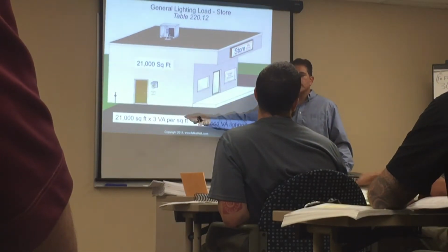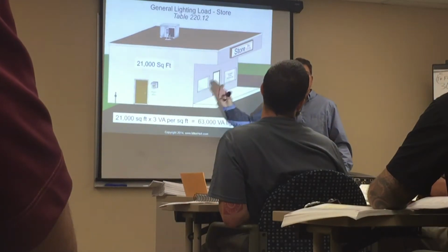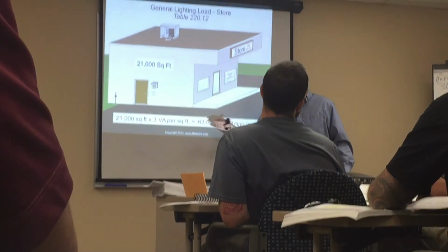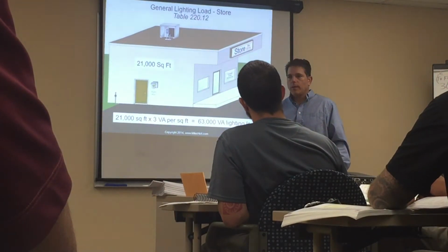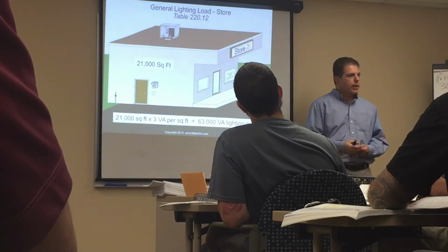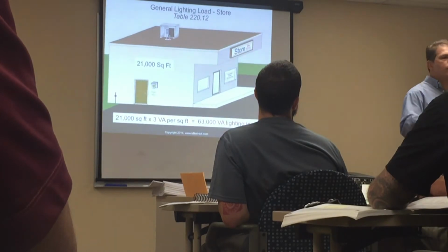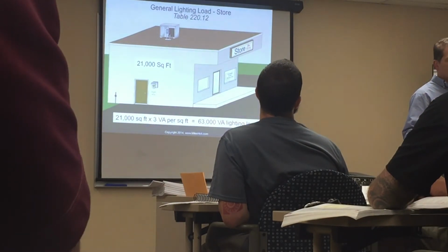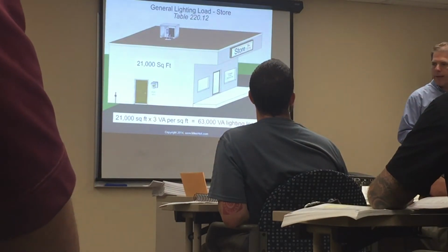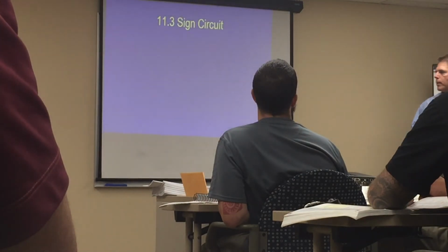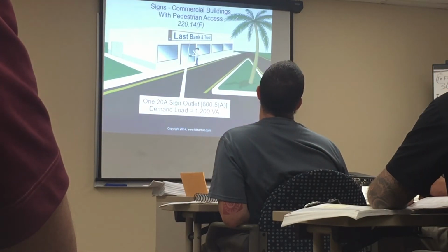Is the 3 volt-amps per square foot larger, or is the actual connected load larger? Whatever one's larger is your answer. That's the load that you would use to calculate the service. It's always the larger of the two. And we'll do a couple of those examples. All right.